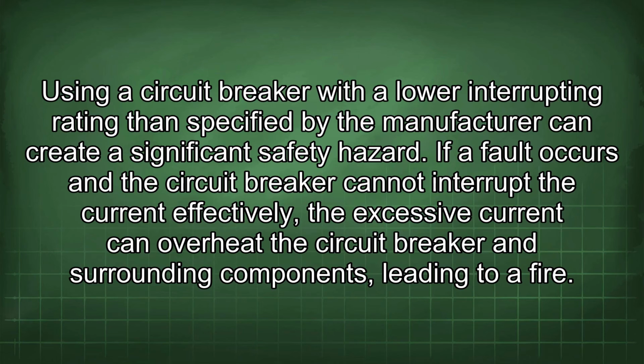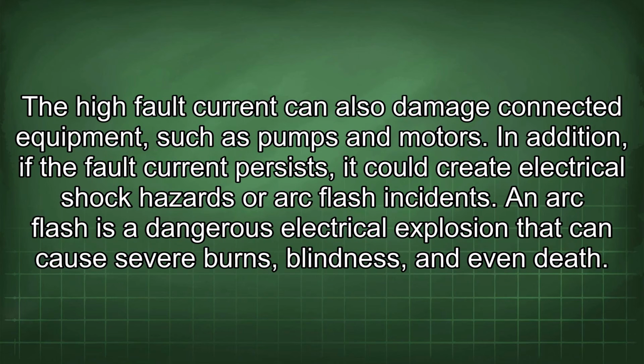If a fault occurs and the circuit breaker cannot interrupt the current effectively, the excessive current can overheat the circuit breaker and surrounding components, leading to a fire. The high fault current can also damage connected equipment such as pumps and motors. In addition, if the fault current persists, it could create electrical shock hazards or arc flash incidents. An arc flash is a dangerous electrical explosion that can cause severe burns, blindness, and even death.